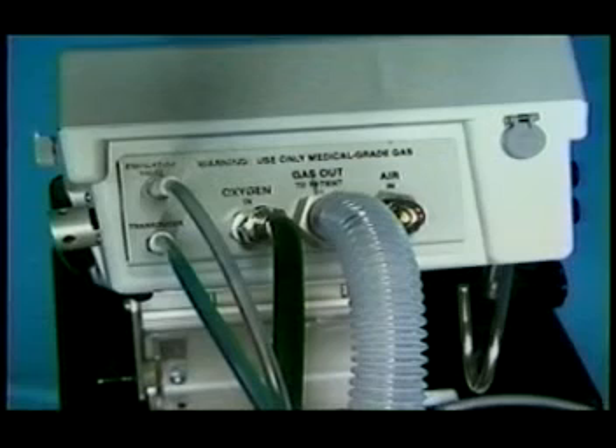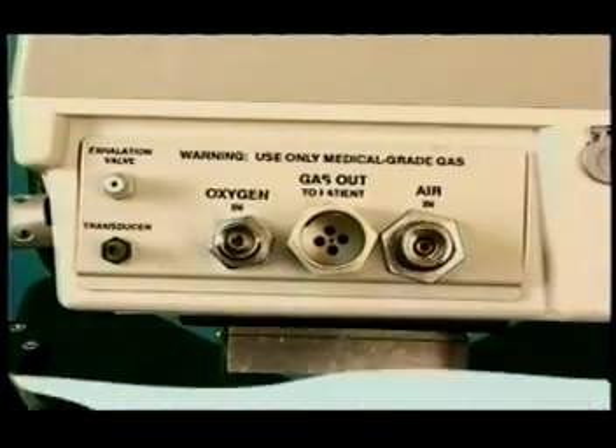The first thing we will do before operating this device is connect all tubing, hoses, and cables. Our choice of gas or gases and operating power determines which hoses and accessories are required. If our use includes external oxygen or external air, remember to use only compressed gas that is rated medical grade. The ventilator contains fittings marked oxygen in and air in. In this case, we'll operate using external oxygen.